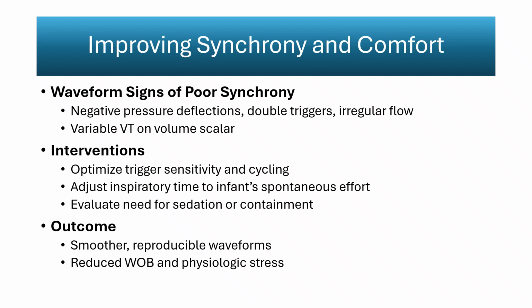Poor synchrony reflects a mismatch between the infant's respiratory effort and the ventilator's timing or flow delivery. The pressure time scalar often provides the earliest clue. Negative deflections before inspiration indicate the infant is attempting to trigger, but the ventilator is not responding. Double triggering or stacked breaths occur when the ventilator cycles too early and the infant continues to inhale, while irregular flow patterns suggest inconsistent support. On the volume scalar, variability in delivered tidal volume from breath to breath reflects unstable interaction between patient effort and ventilator assistance. Management focuses on restoring alignment between the ventilator's breath delivery and the infant's native rhythm.